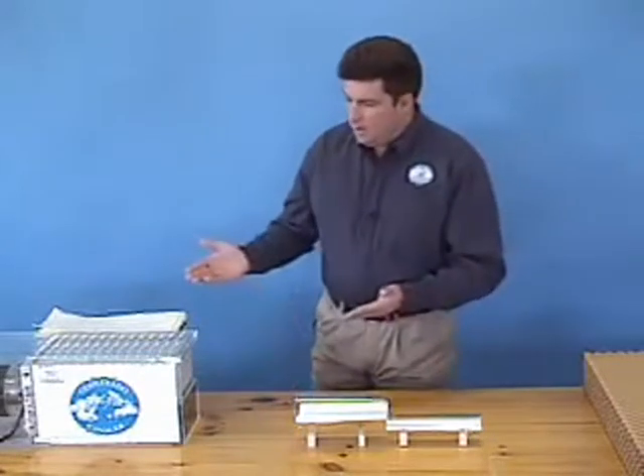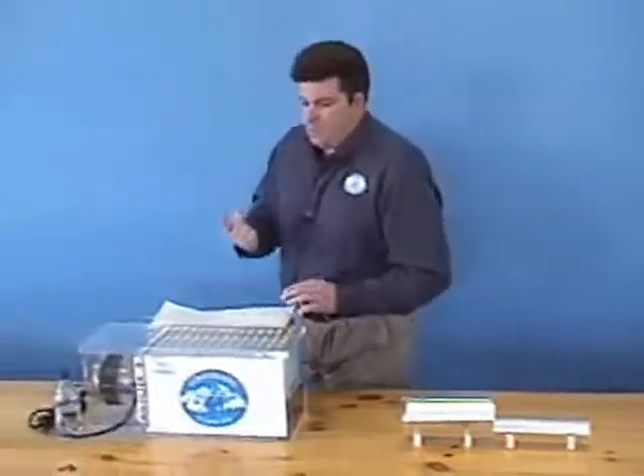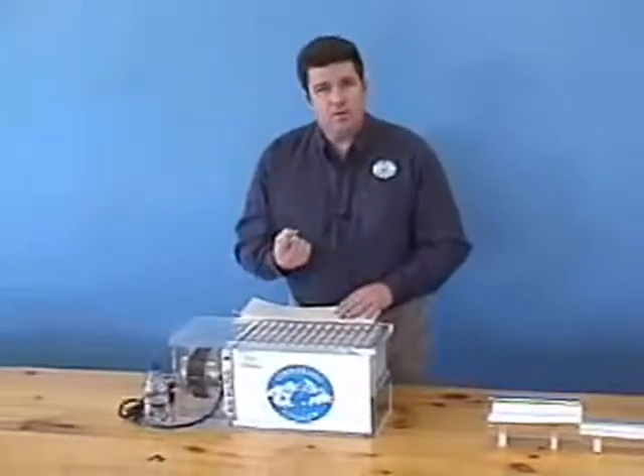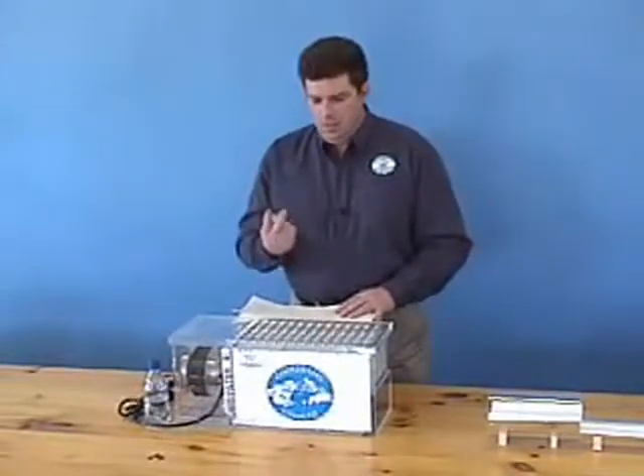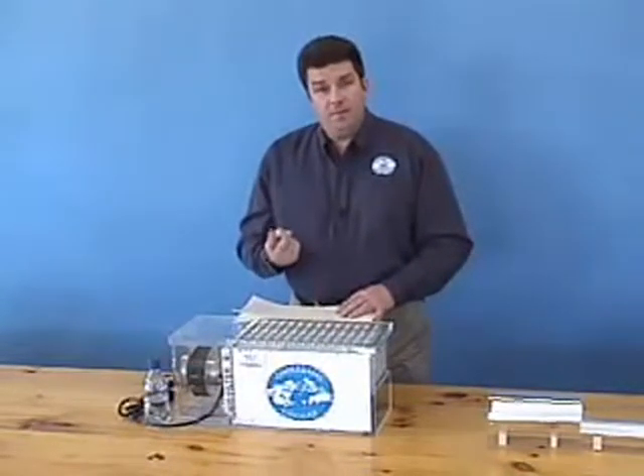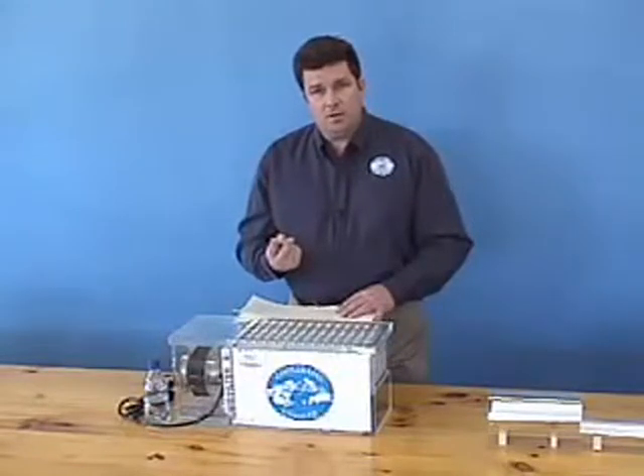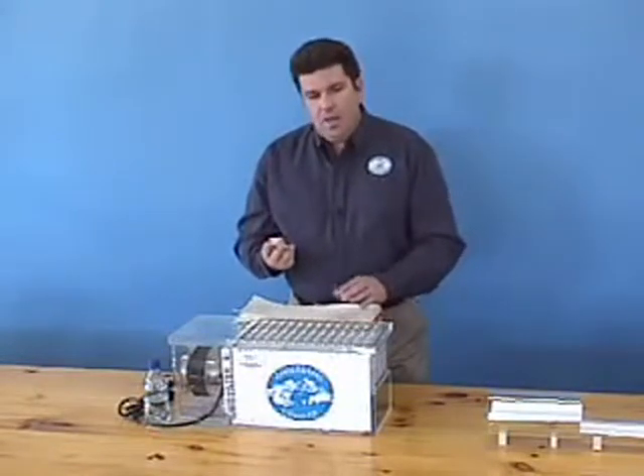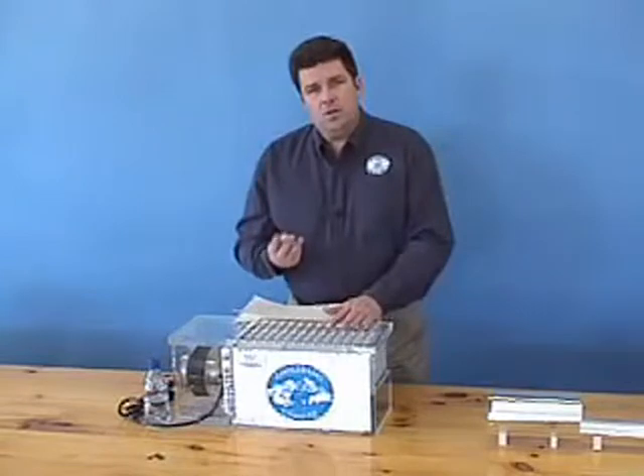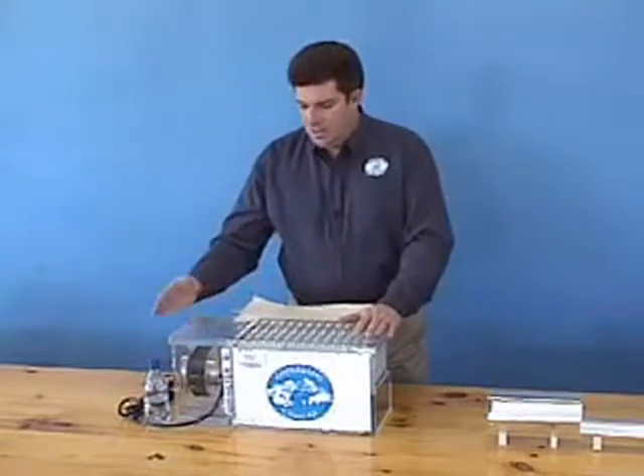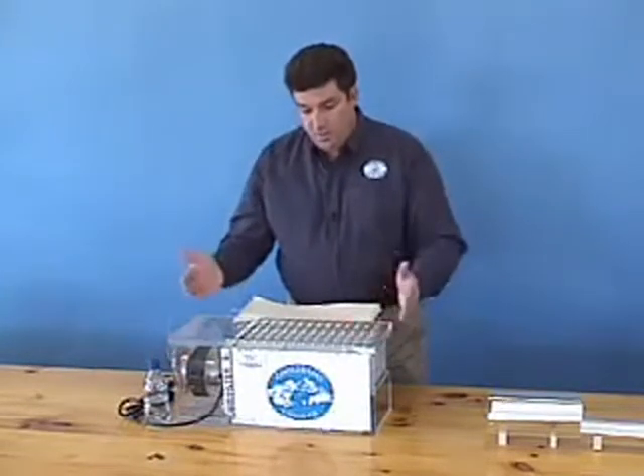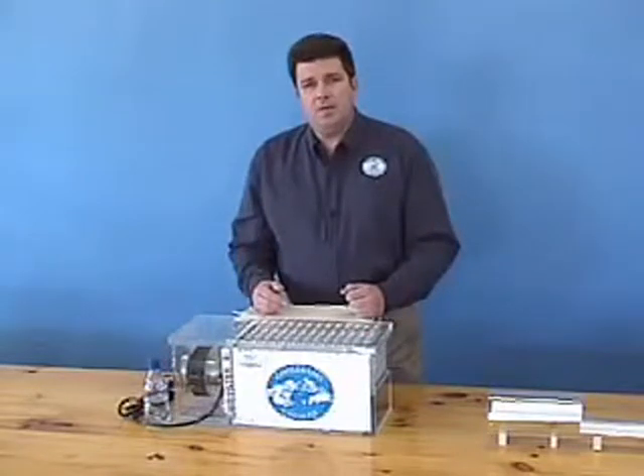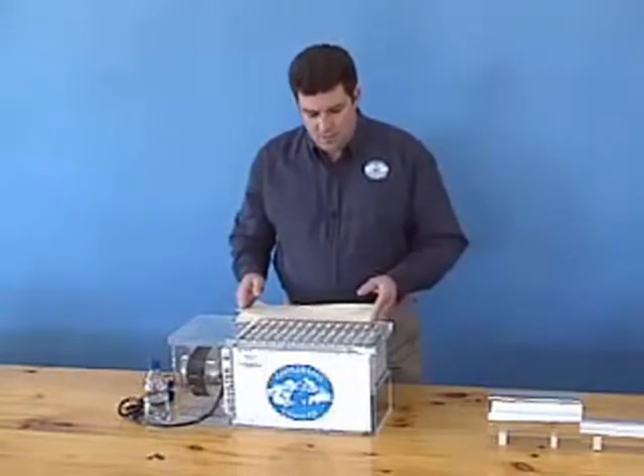But Coolerado coolers have a small pressure drop loss, less than a 1-inch column of water. We only throw away about 50% of the incoming airstream. And we can cool toward the dew point temperature of the incoming air. With this knowledge, you can begin to understand the pure genius of the Maisotsenko cycle.